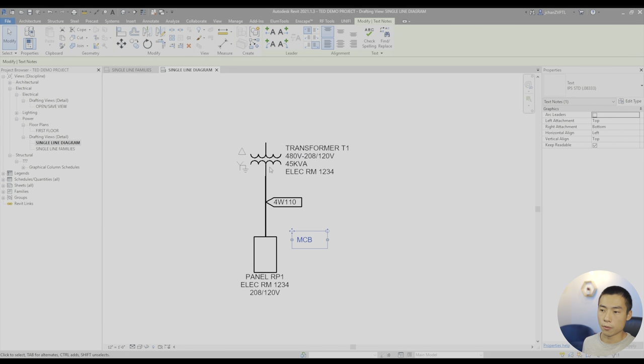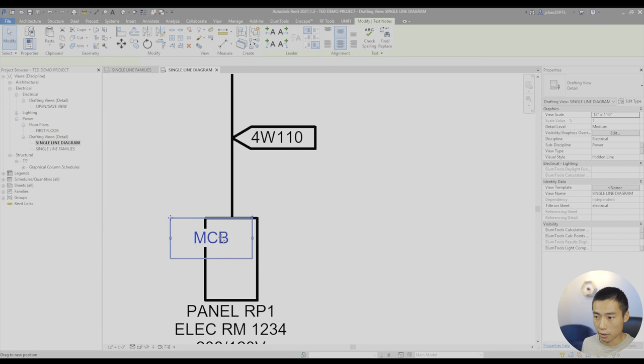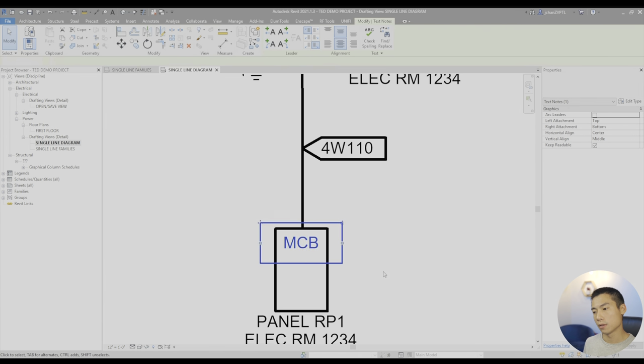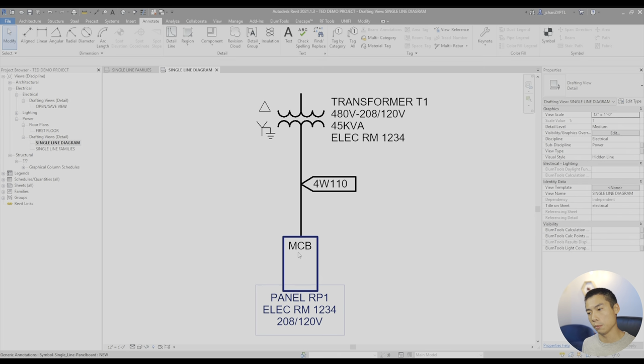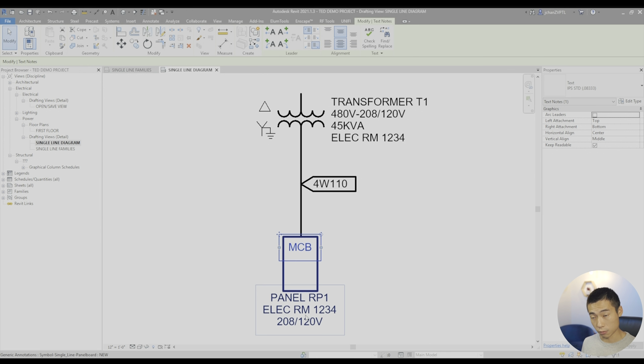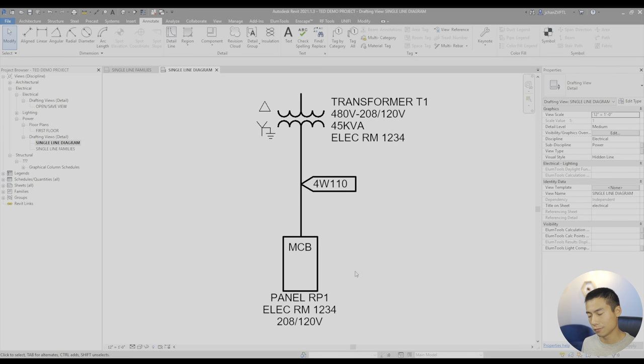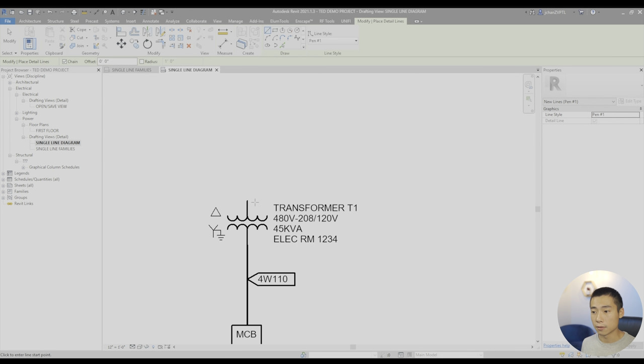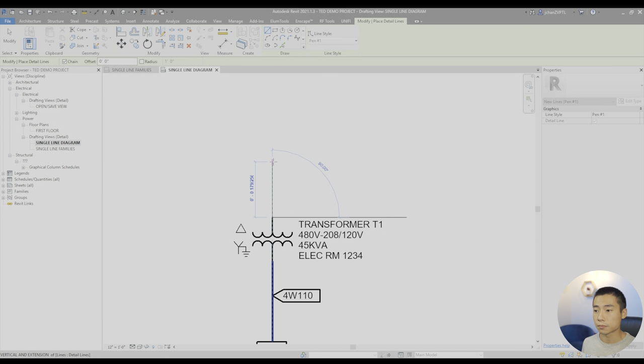So after a transformer, you always need a secondary protection within 25 feet, so that means this panel needs to have a main circuit breaker. So I like to put that there. It clarifies to the permit people that they know we are protecting that. Otherwise, you'd have to go to the panel schedule to figure that out, and it could just be a little annoying.